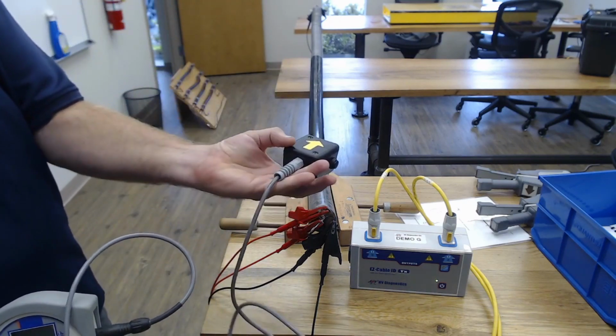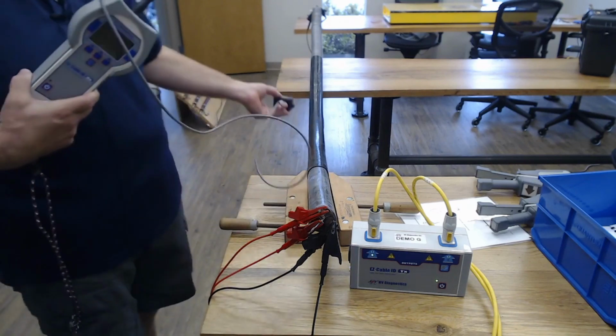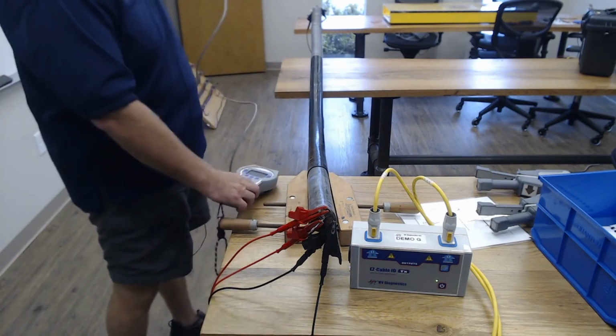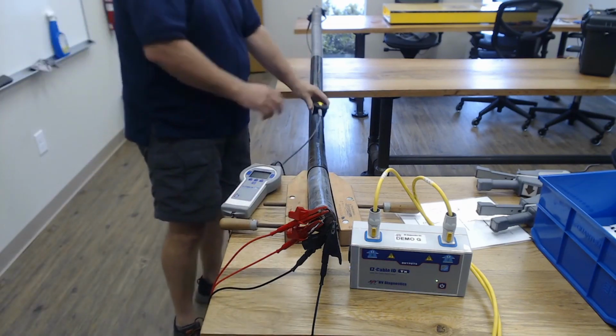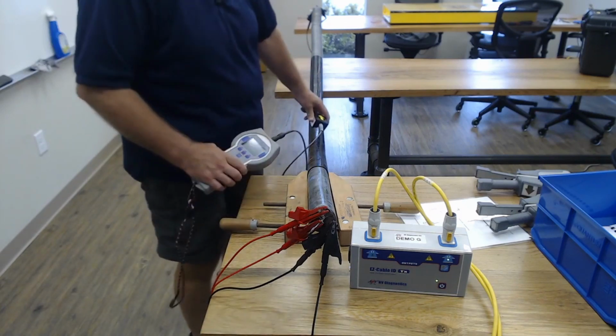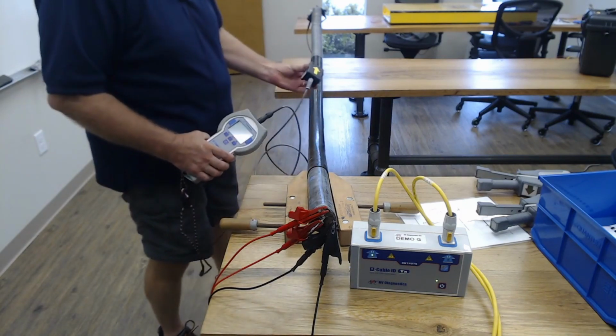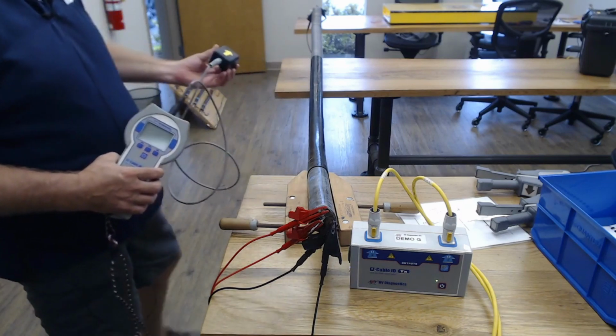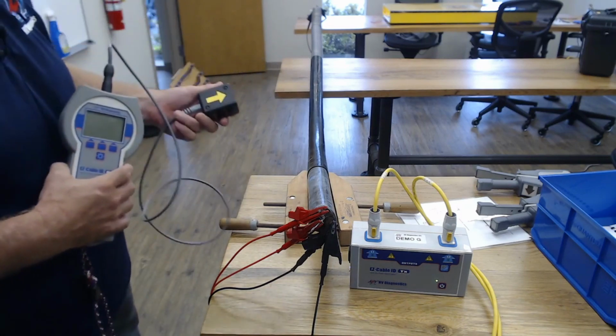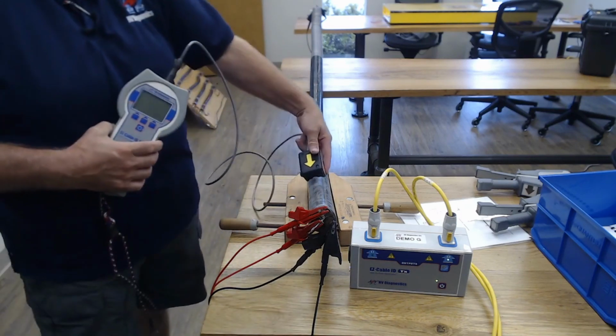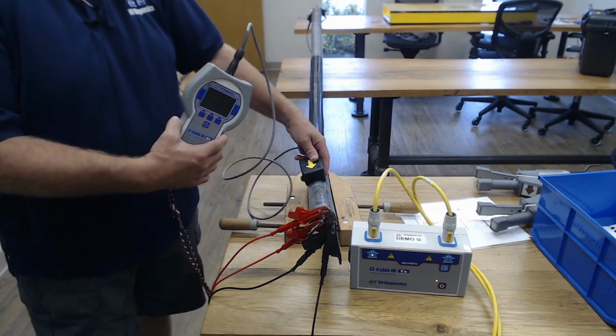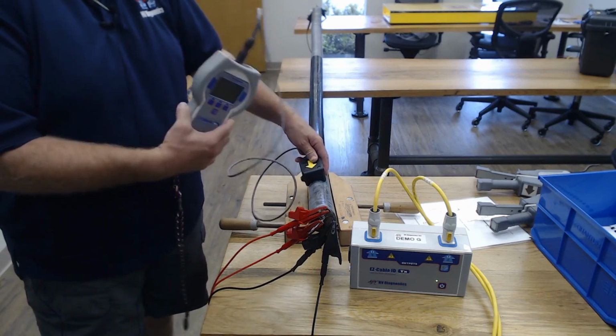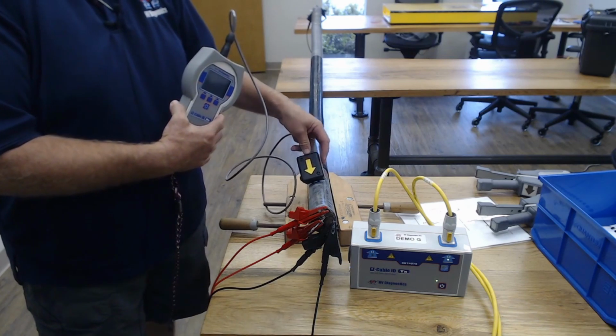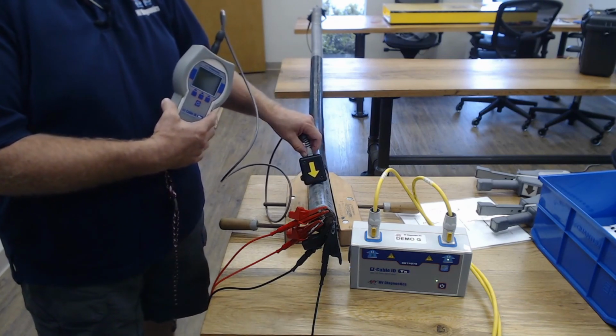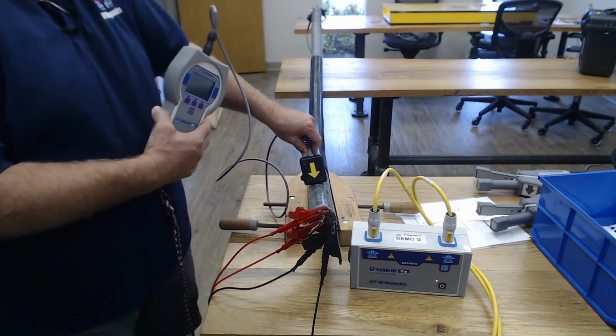Again, the arrow is important. We want the arrow because we're going down, in our case, to the far end. We want the puck to go around the cable with the arrow facing down. Again, for those of you who are used to facing the arrow towards the transmitter, we can set the receiver to accommodate that as well. So both methods of operation are optional and you can set them.